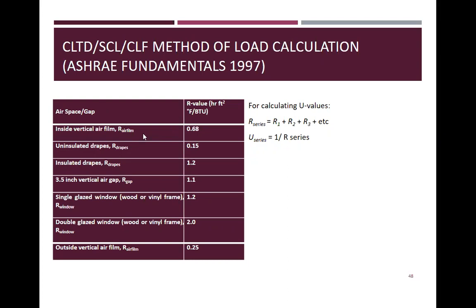So inside vertical air film is 0.68. Uninsulated drapes 0.15. Insulated drapes 1.2. 3.5 inch vertical air gap. Yan 1.1. Single glaze wood or vinyl frame is 1.2. So double glaze is 2. Outside vertical air film is 0.25 kasi may velocity, may wind speed.